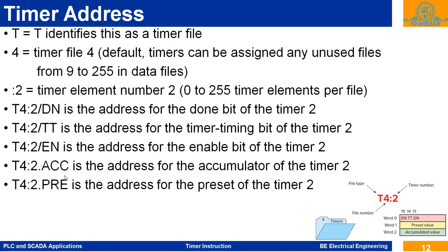In the ladder diagram, we can show the time elapsed from the accumulator, or enter the preset value from the HMI. We can directly write this address on the HMI, and enter the decimal value from there. That decimal number is stored in binary format in the 16-bit preset register of the timer.